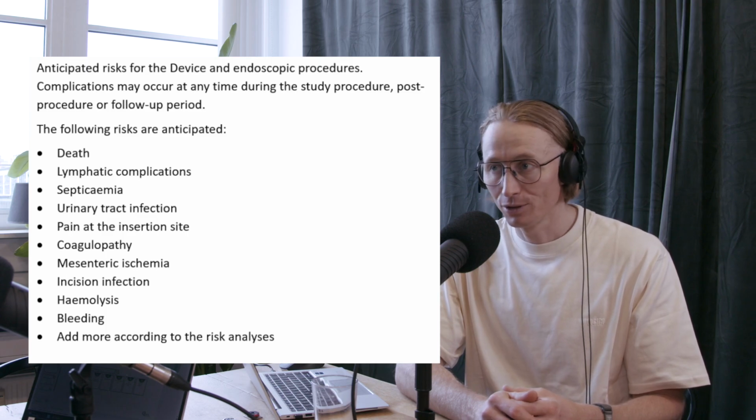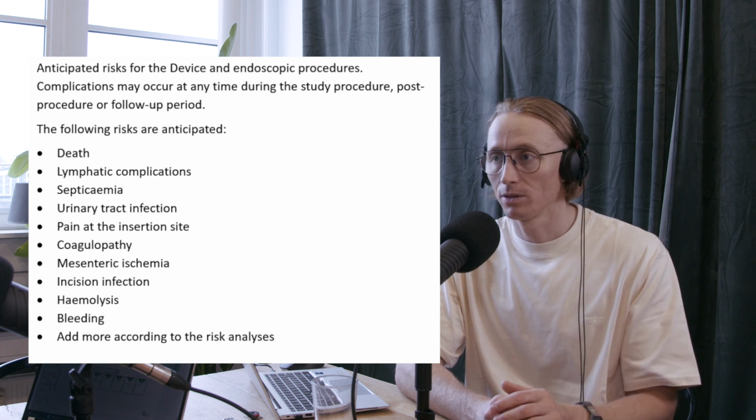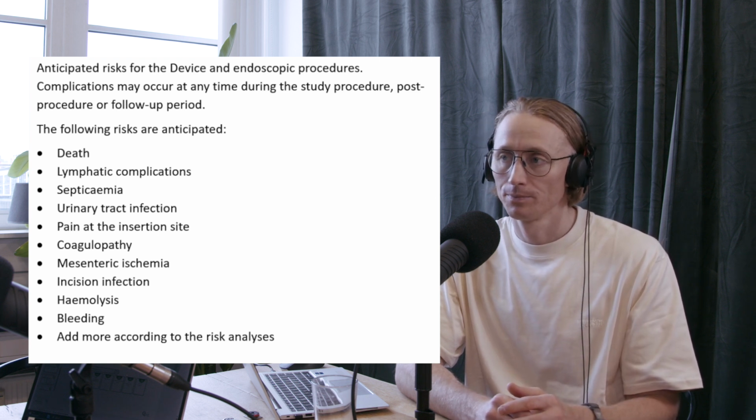And then what you see is when you start to develop your risk analysis, that you would have the same harm coming up again and again. And that is actually a good thing. So in the end, what you create is a list of harms. And those harms should be visible in your IFU. So you actually need to show to your user and probably also patients what harms can actually come of this device. And we are not talking procedure harms. We are talking device harms. What harms does your device create?